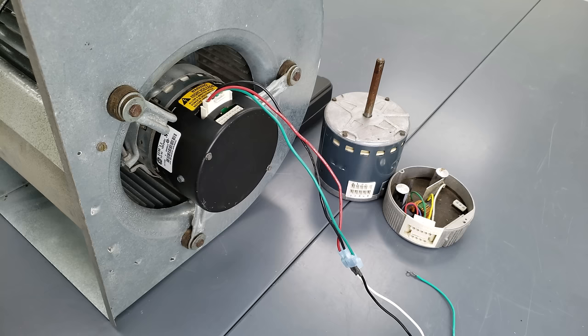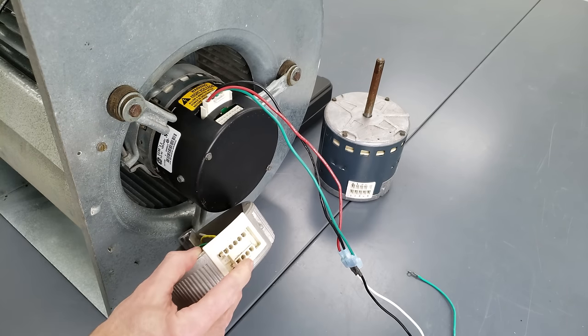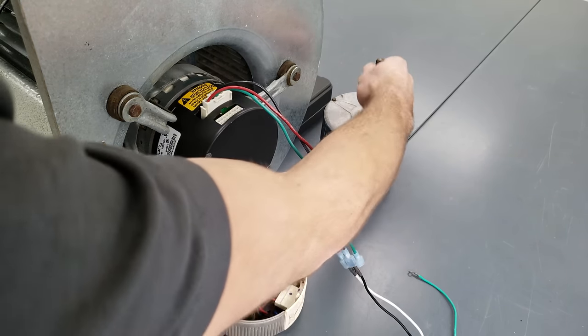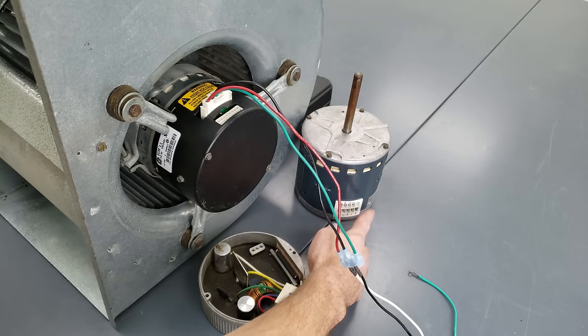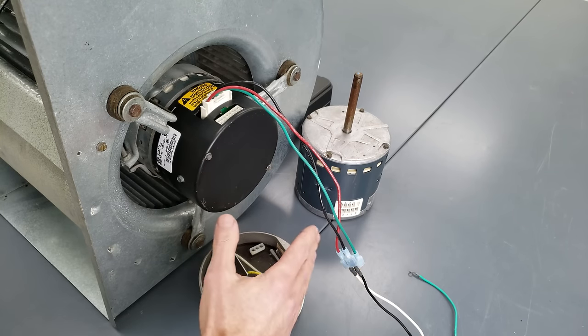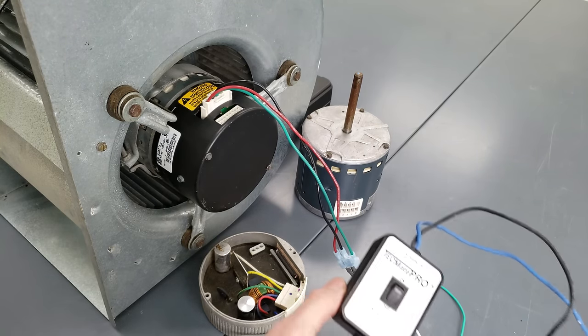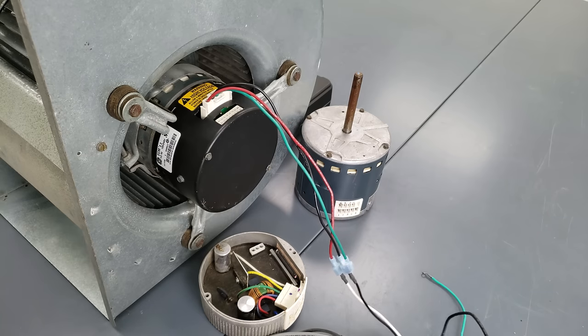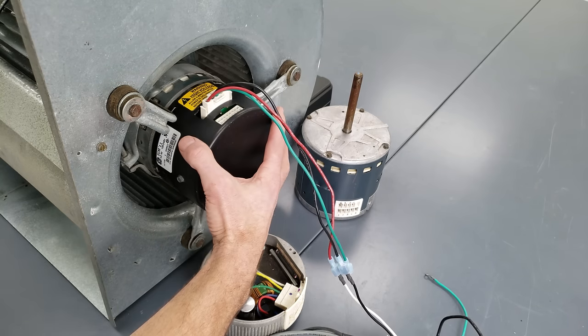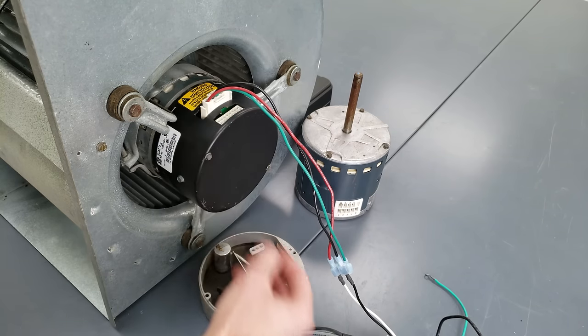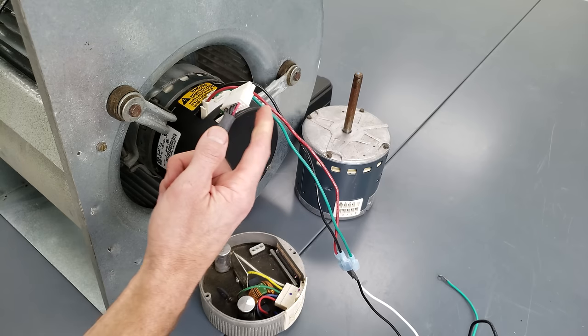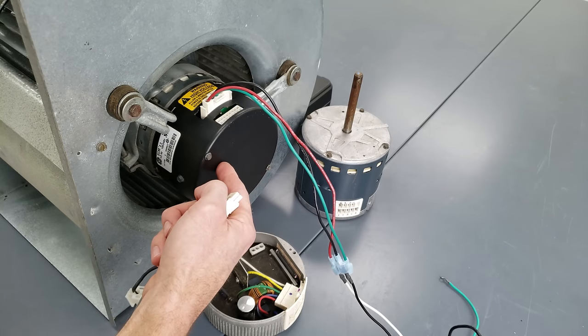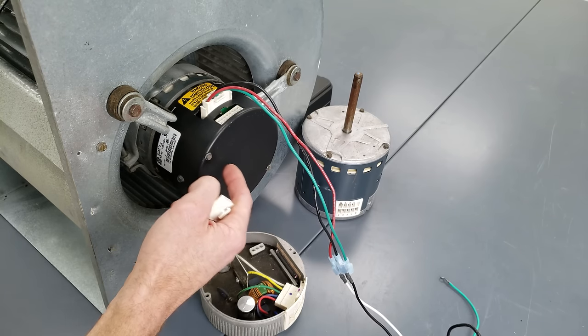And so once again, that's a 2.3. This is a 3.0 version. And here we have an X13 model. So that's an ECM multi-speed motor. What I'm going to do for this test is use a TechMate Pro in order to signal this blower motor to turn on, and I'm going to show you what happens even after I remove the control. This particular ECM motor is just going to continue to run.